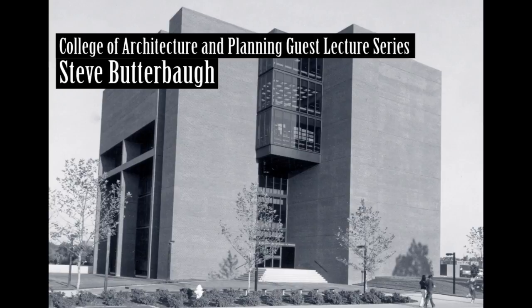The computer would take this basic data and build it up into a composite figure of kilowatt hours and BTUs. We would check these figures against the billings to see if we were close or whether there had been an error. At the same time, we submitted the data for the existing building. We submitted the data for the changed building. If we cut lighting 50%, we so indicated. If we changed fuel source, we so indicated. If we changed the building skin, we had different heat gains and losses.